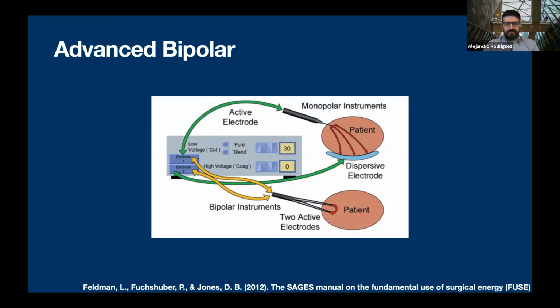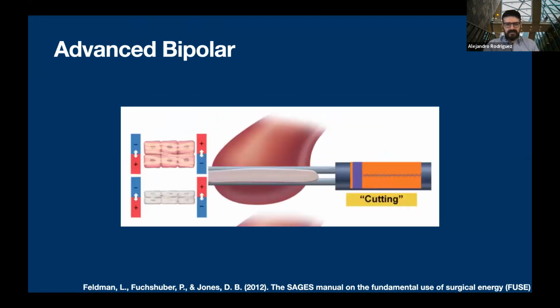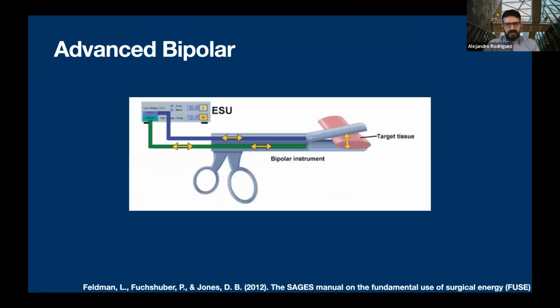Advanced bipolar devices are newer iterations of the same technology. This works much like your basic cutting setting, in that it produces a low voltage continuous wave that causes tissue evaporation rather than desiccation. When you apply this to tissue crushed between the bipolar clamp, you get a good tissue seal — that's the basic functioning of it.